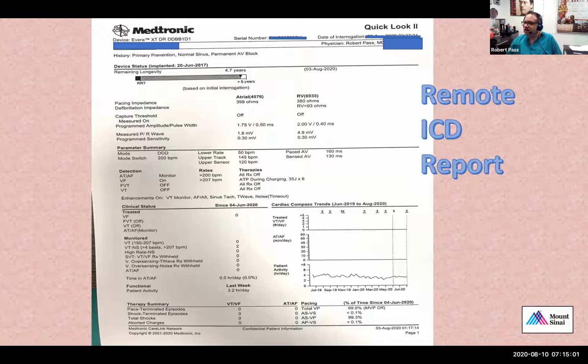The next thing you see on that list is the defibrillation impedance, which in this case is 93 ohms. Every single defibrillator lead has a range of defibrillation impedance that is considered acceptable. In this case, this is on the high side, but it is still an acceptable shocking impedance. And so that is an indication that the coil, which is used for shocking, and the lead in terms of its shocking ability is intact, at least according to these measurements.